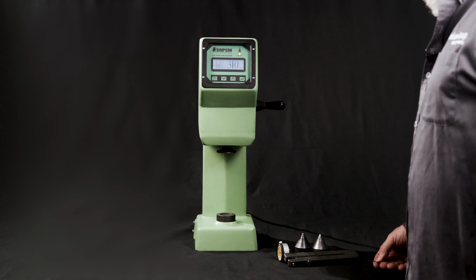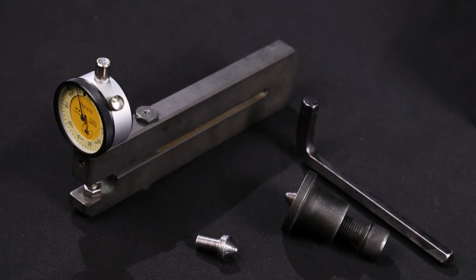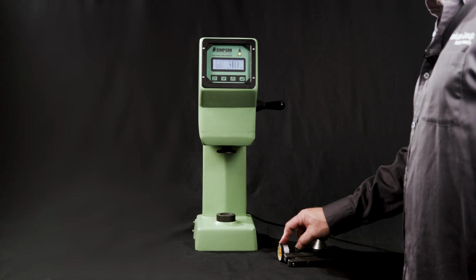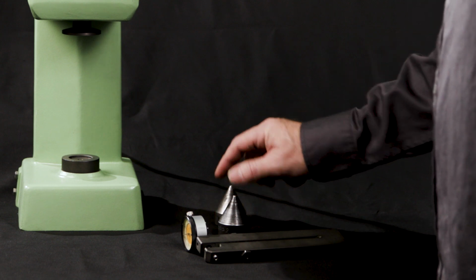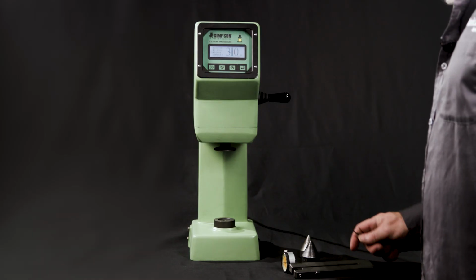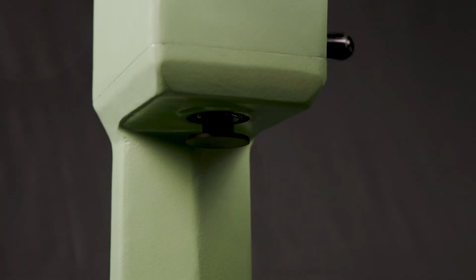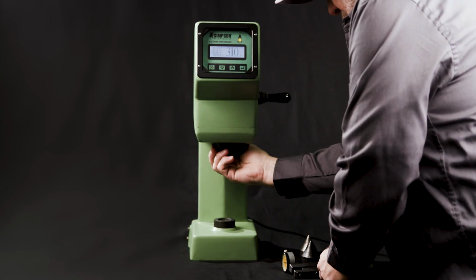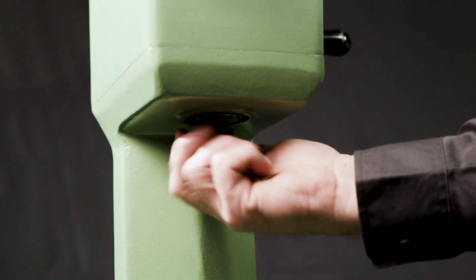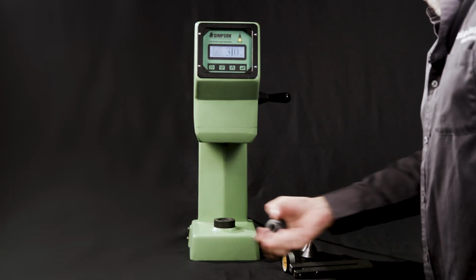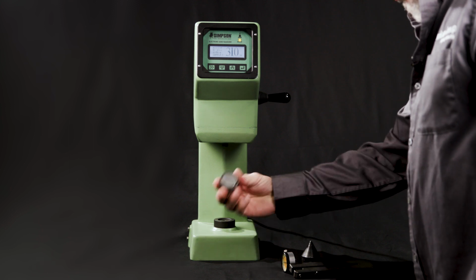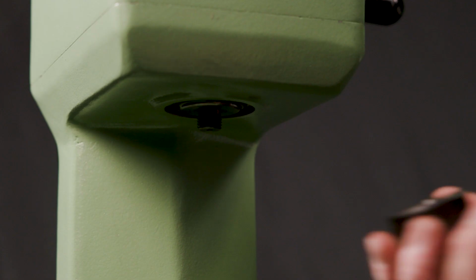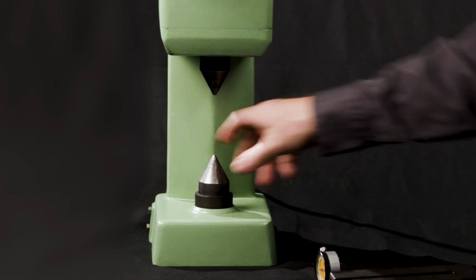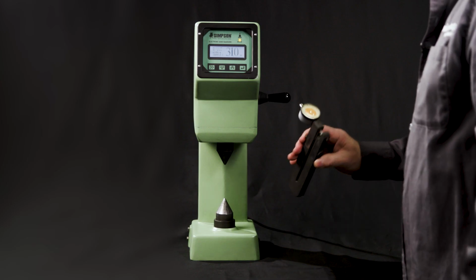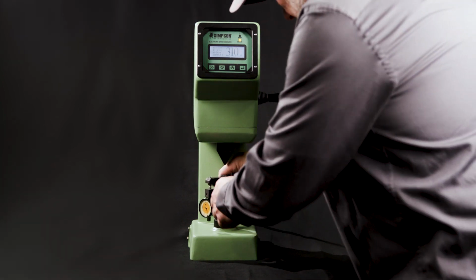So for the electronic sand squeezer, the final calibration that we need to do on this machine is the final pressure set point. We are going to use a mechanical load cell to set the air regulator pressure for a certain millimeters of deflection on the manometer of the mechanical load cell using the pressure cones that are purchased separately. So the first thing that we need to do is we're going to remove the foot of this machine. There is a set screw that we loosen, and then we unscrew the basic foot at the bottom of the piston. We're going to move that to the side. We have 2 set bottoms for the cones. This one is for the screw onto the bottom of the piston, and the other one fits onto the base assembly of the equipment.